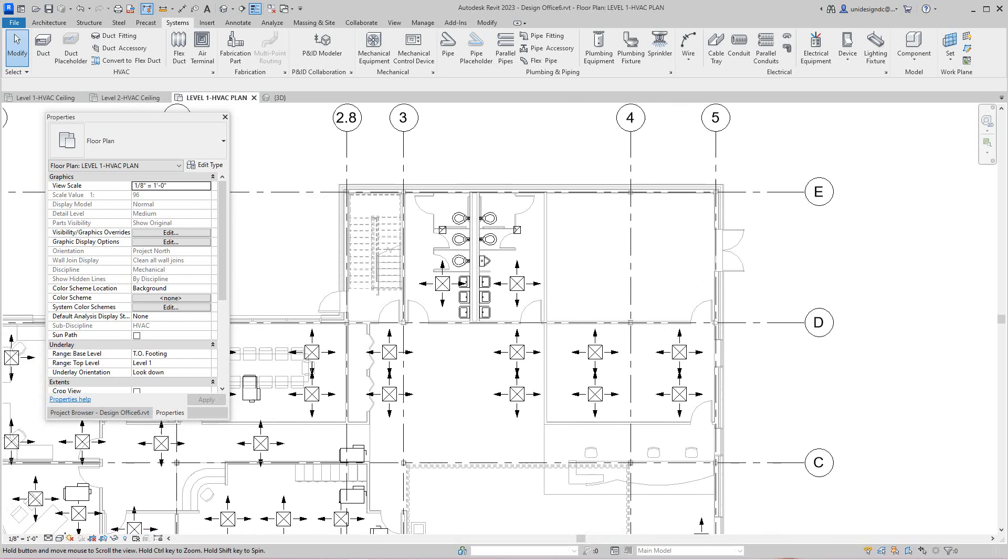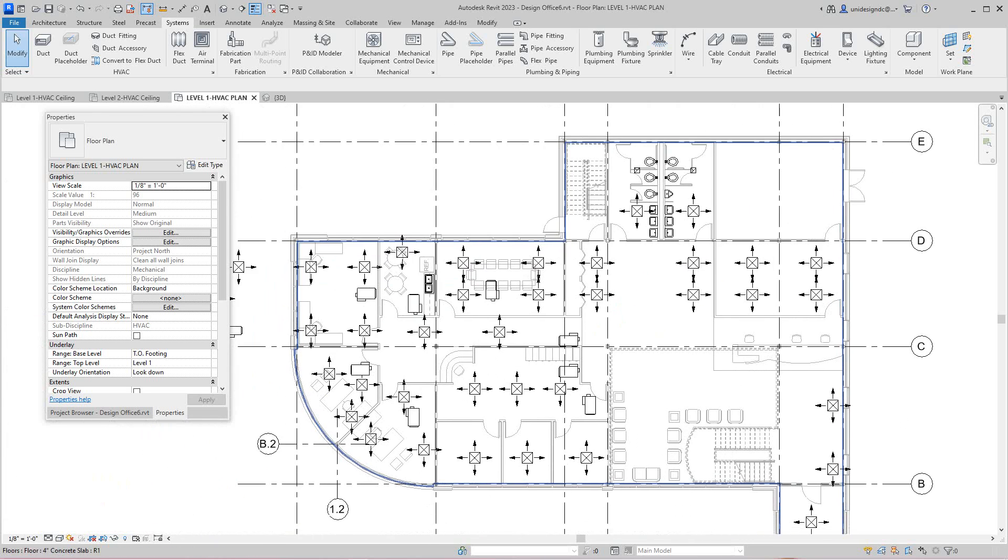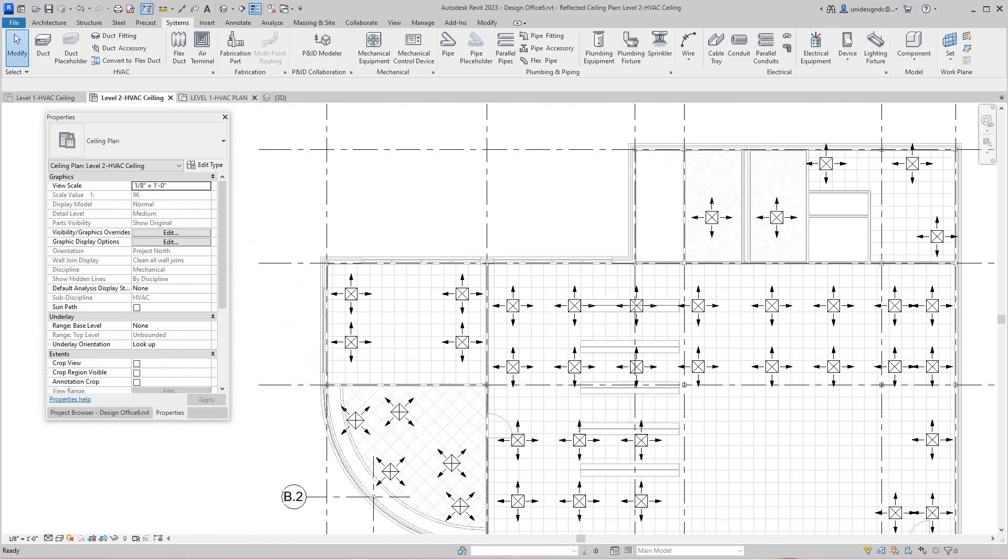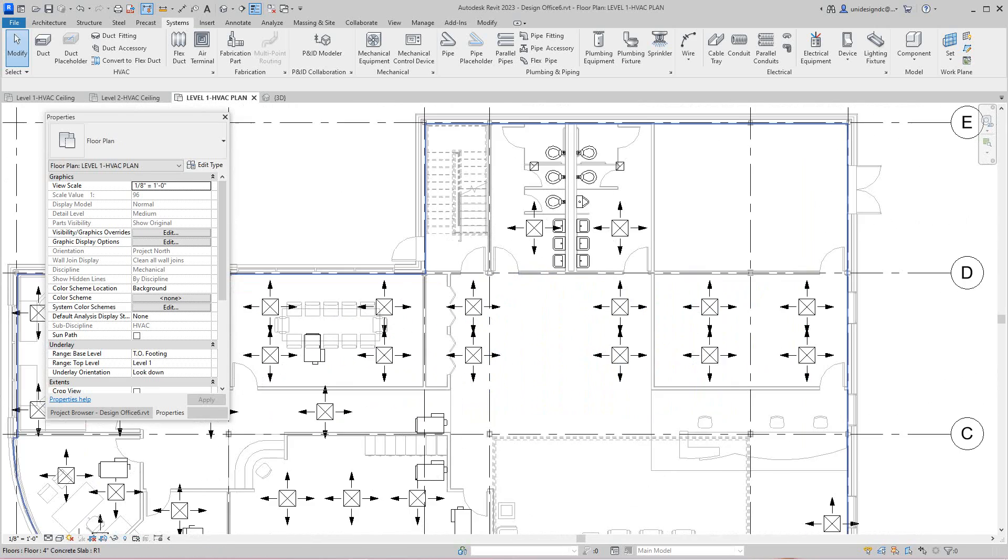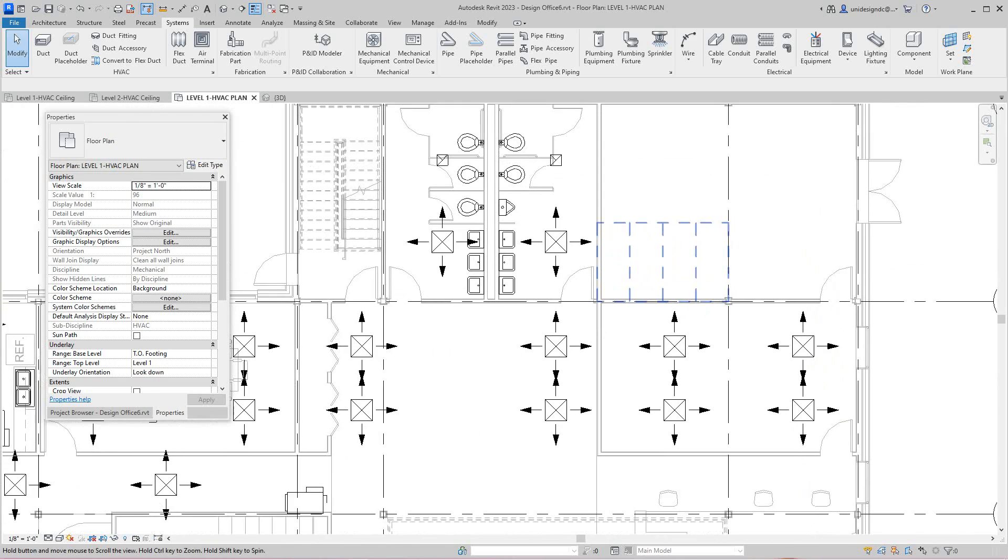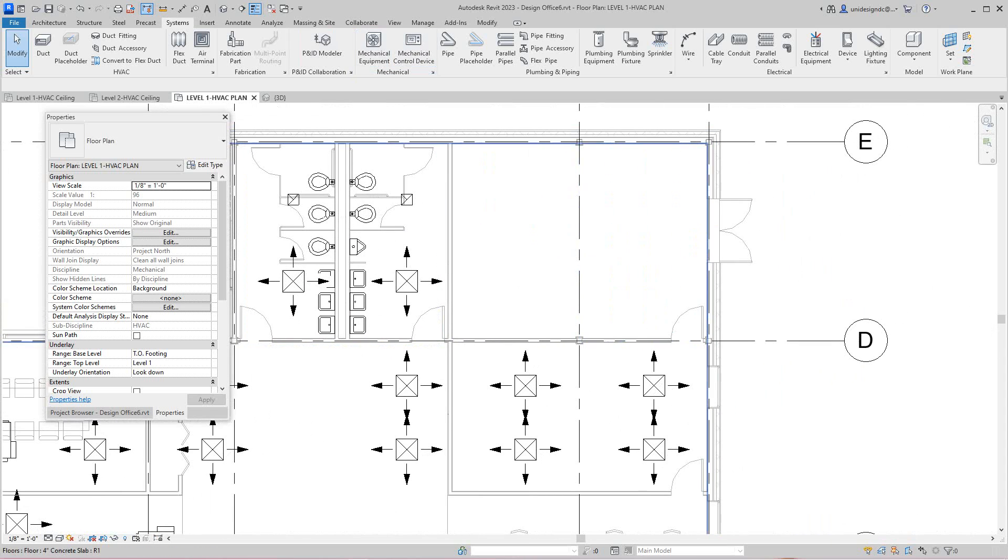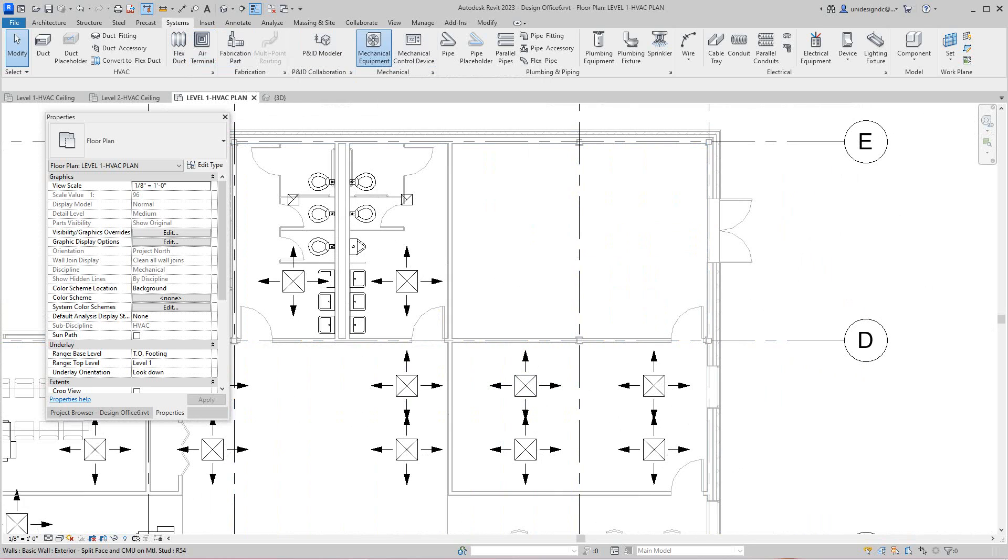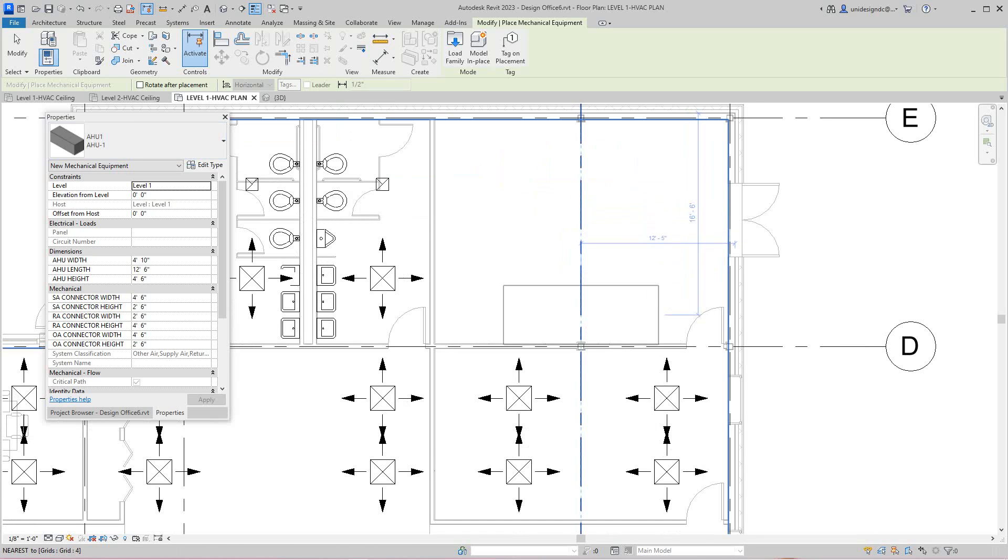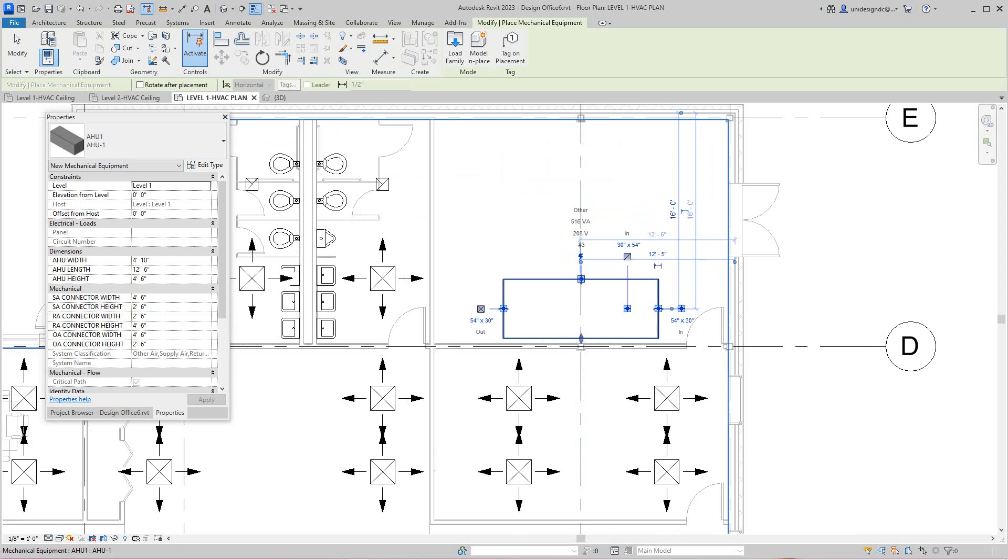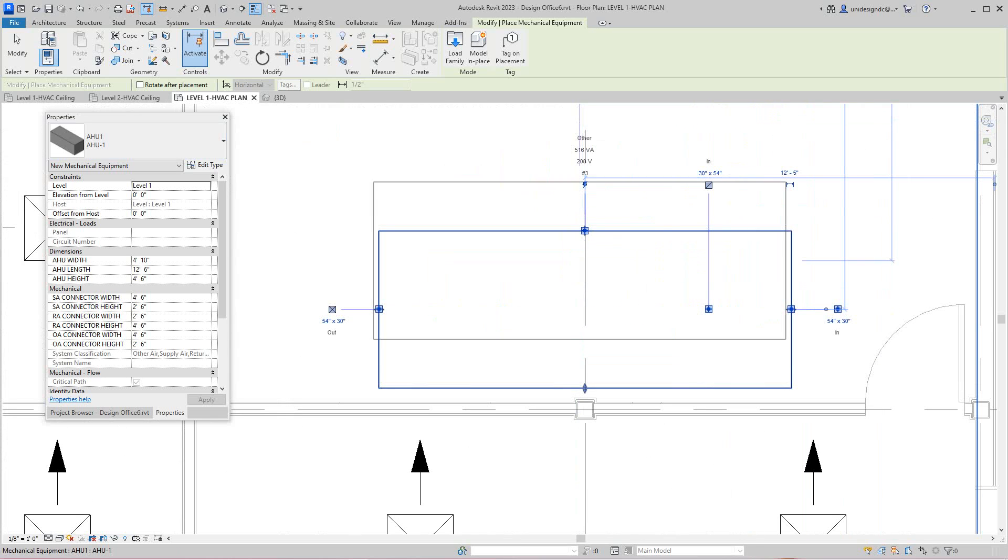This is a very fun exercise. Now we're going to look at mechanical more in-depth. We've got to get our air handling unit in here. As you see, I got all my diffusers in both levels. So what you want to do here is go to my systems and here's mechanical equipment. Here's my air handling unit. It's just a 3D box with connectors on it. As you can see, these connectors correspond with sizes and the types of ductwork that will come off, whether it's supply here, return, or outside air.